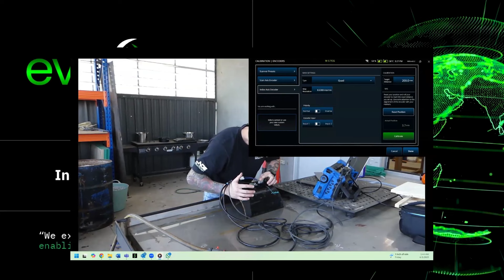So when you're setting these scanners up here, it's quad. You're not doing any click or anything. And we're capturing data mil by mil for this inspection here. So I'll just repeat the same process. We've got VPA lines on the side of the dual, which I'm using for my reference point to know that I'm 0 and I moved it 200. I'm just lining that line up on my marks on the pipe there. Forgive me, I'm using a paint marker, so we do have some width to the tip. But yeah, we got that resolution dialed in pretty good here.